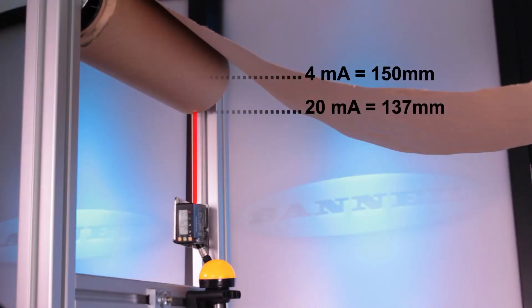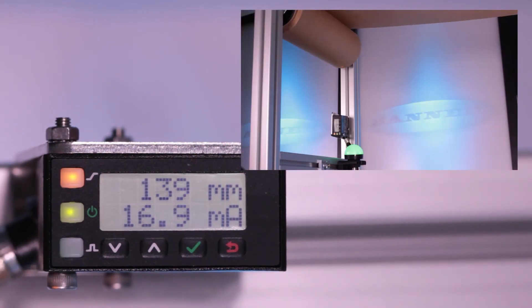The analog output is set from 137mm to 150mm with a negative slope, so as the roll unwinds, the analog output will decrease.